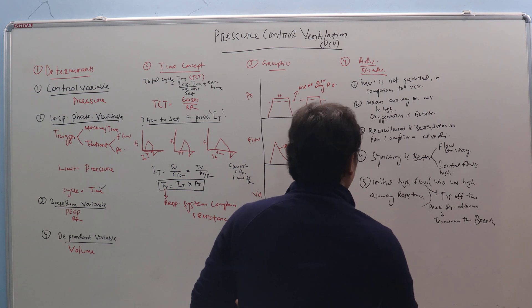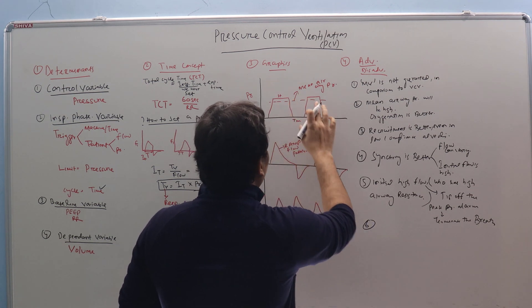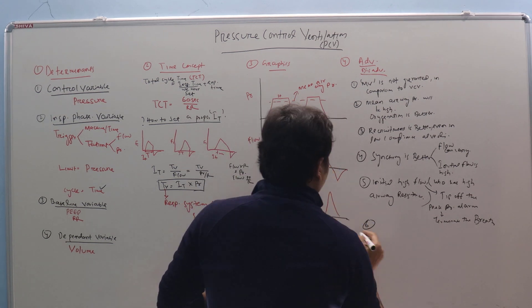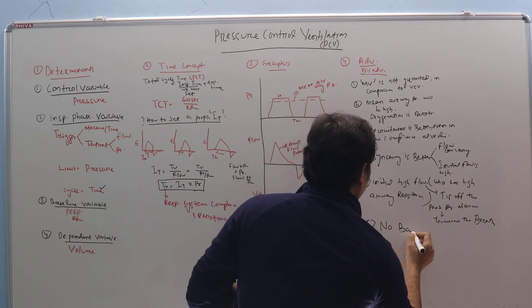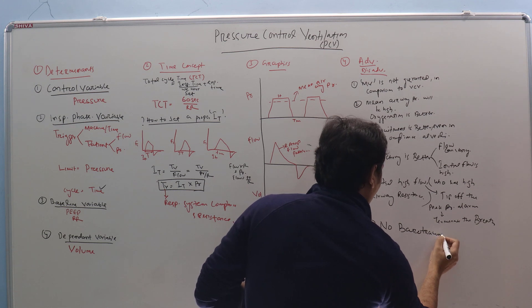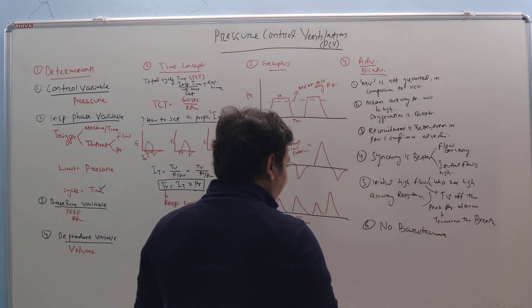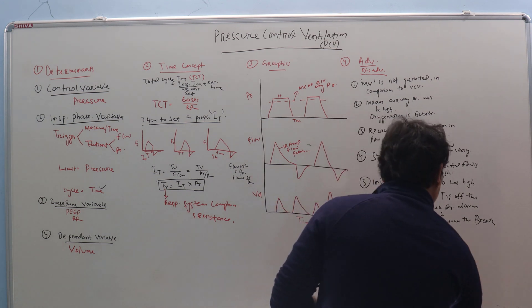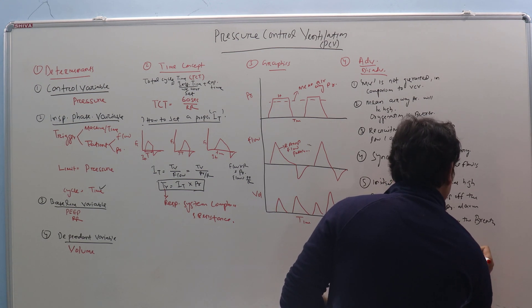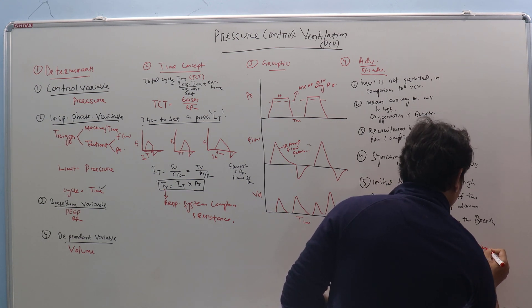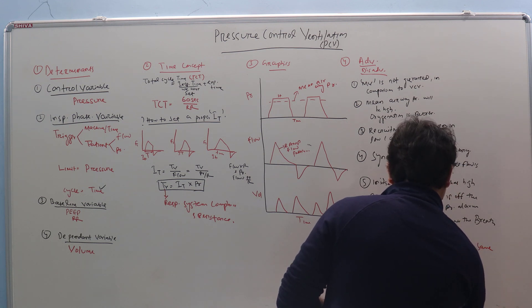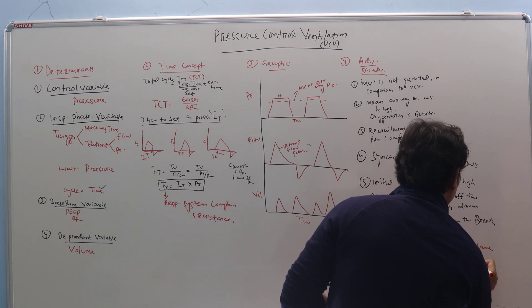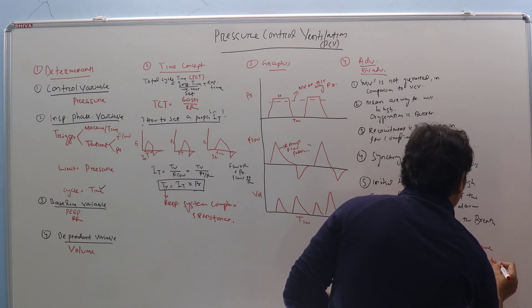Sixth advantage: there will be no barotrauma because you have controlled the pressure. However, if the compliance of the lung improves, the same set pressure can deliver a higher tidal volume, potentially producing volutrauma. So one must monitor tidal volumes carefully when lung compliance changes.